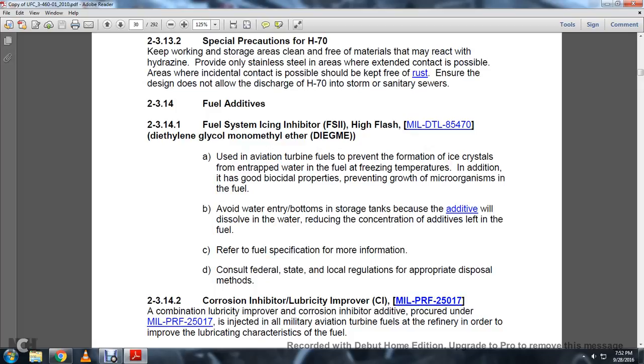All right, 2314 Fuel additives. 2314-1 Fuel system ice inhibitors, high flash, detailed specification 85470, diethylene glycol monomethyl ether. Used in aviation turbine fuels, preventing the formation of ice crystals from trapped water. It keeps the fuel from freezing at low temperatures, in addition to good biocidal properties, preventing growth of microorganisms in the fuel, and avoids water entry at the bottom of the storage tank between the additives that will dissolve water, reducing the concentration of additives left in the fuel. Refer to the fuel specification for more information.